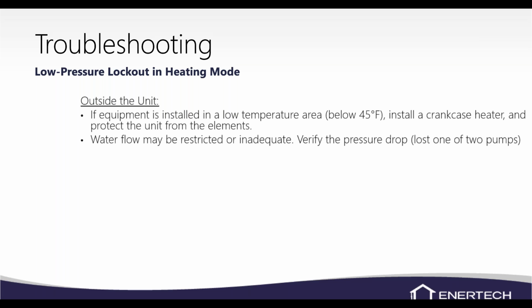Water flow, again, we're looking at the source side. Look at your water flow. Check pressure drop. Make sure you haven't lost a pump. Make sure that the water temperature is not too low and it's freezing up. You could have low antifreeze, so make sure we're checking our antifreeze levels and our water temperatures as well.